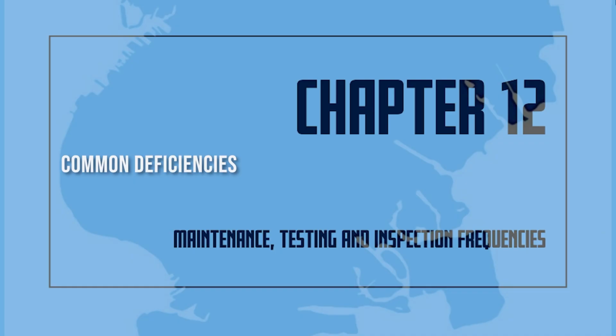Installations that don't appear to be correct, including sprinkler heads located more than 22 inches below the ceiling or structure, sprinklers not installed in accordance with their listing, using sprinklers with a different RTI in the same protected area or the wrong RTI for the occupancy classification, undersized piping, incompatible piping materials, flexible sprinkler hoses not attached to the building structure, along with areas of the building not protected by the sprinkler system. All require further investigation by a qualified master fire suppression piping contractor.